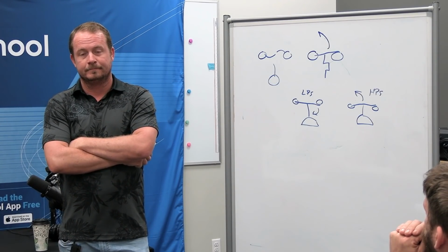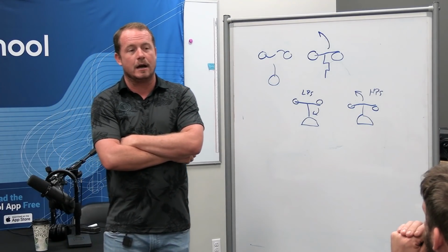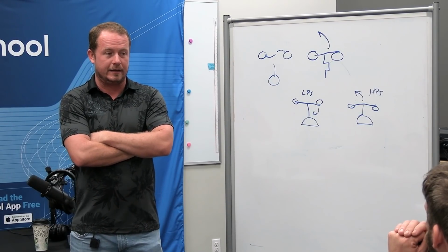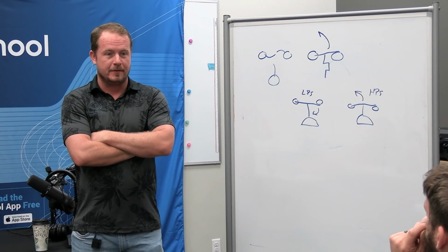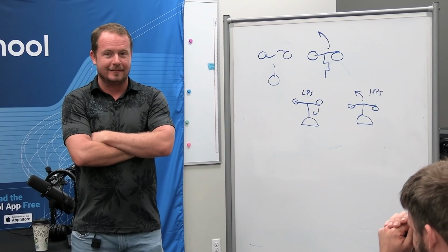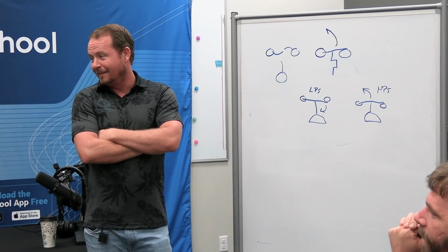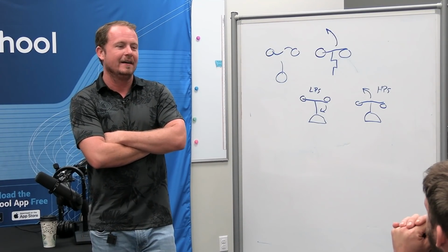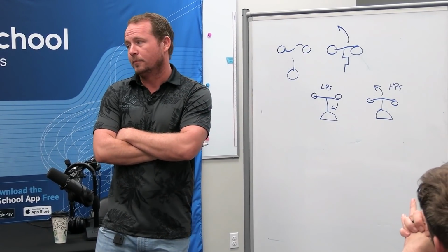Failed TXV on the high pressure switch is pretty unlikely, and that goes into a complicated topic about restrictions and what happens when a system is restricted, but possible, unlikely. What else? Evaporator coil dirty. Failed TXV on a pool heater. Low water flow on a pool heater, for sure.